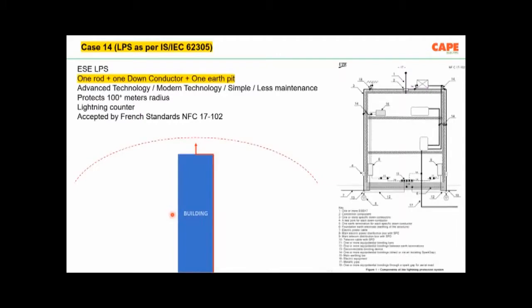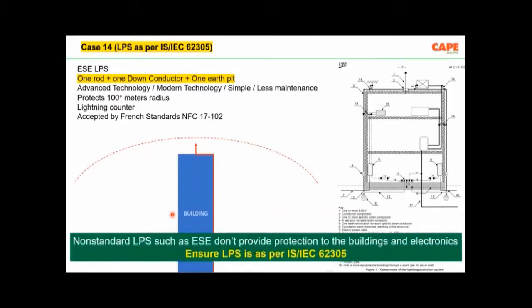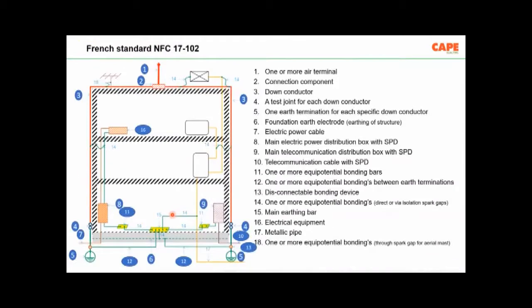When it comes to lightning protection, all of you know that most of our critical electrical installations, such as the metro rail, S&T buildings, the SCADA centers of the power transmission companies, or the data centers, in a lot of places still use early streamer emission devices for lightning protection as per the French code NFC 17102. But please understand the early streamer emission standard, the NFC 17102. The picture which I am showing is how to install an early streamer emission device. Early streamer emission is not a magic device which attracts lightning from 100 meters and sends it directly to the earth through one down conductor. This one rod, one down conductor, one earth electrode is actually a foolish idea.